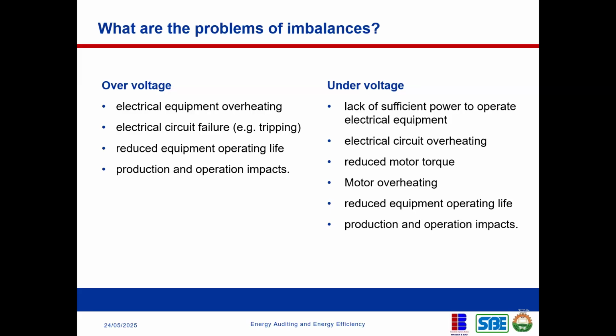There's also electrical circuit overheating, and reduced motor torque. In my house, I have a solar system, and when I'm on the grid, my fan speed reduces. But when I'm on solar, because it gives the standard voltage, the speed increases. When I go to the grid, the rotation reduces because the voltage isn't at the standard level. For industrial applications, motors get overheated, equipment operating life is reduced, and there's production and operation impact. These are the problems that happen with imbalance in voltages.